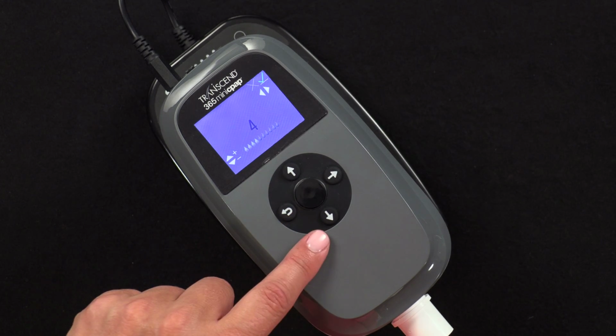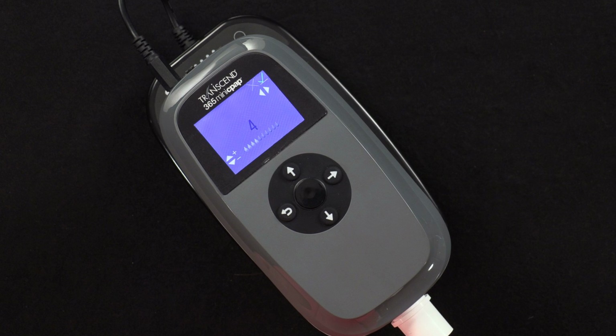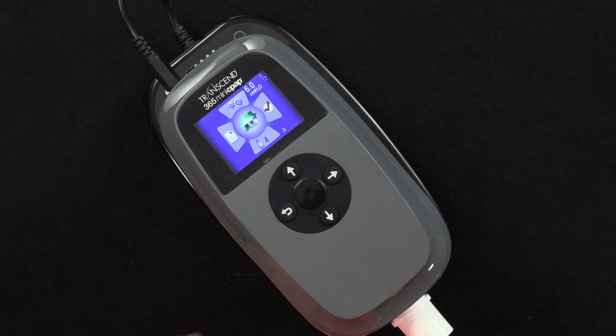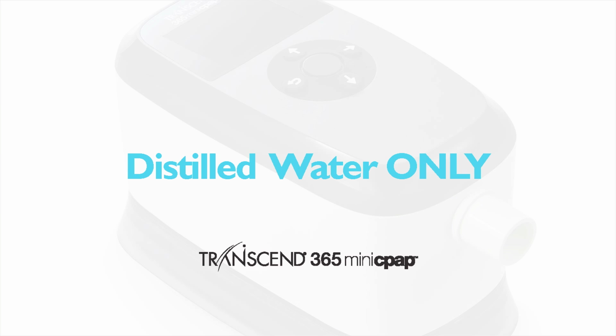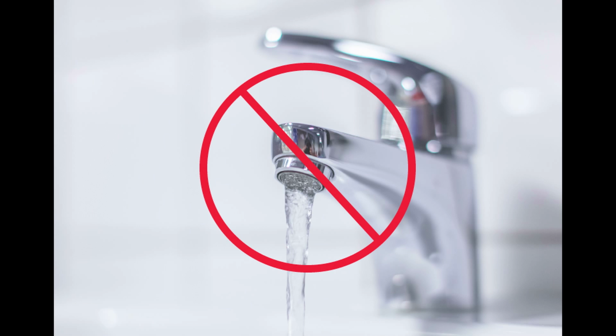Arrow down to the droplet icon and press the center button to view or change your humidifier settings. The up and down buttons adjust the humidification level. Settings range from 0 to 10. 0 turns off the humidifier. Make sure to highlight the green checkmark and press the center button to save your settings before returning to the home screen. It's important to note the Transcend 365 Mini CPAP only uses distilled water, or water that's been filtered with the approved Transcend 365 portable water filter. Do not use tap water or you will damage the humidifier. We'll cover how to use the accessory portable water filter in a little bit.